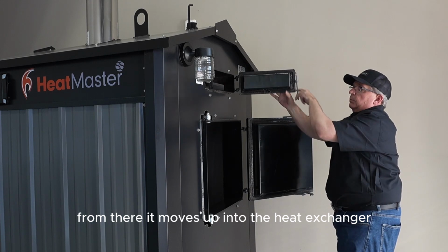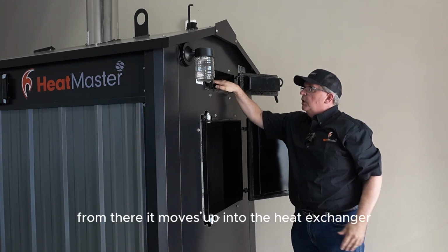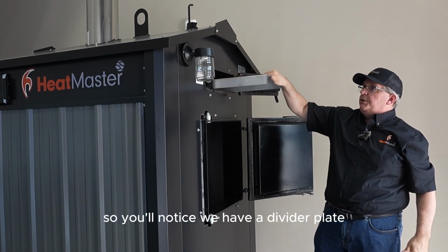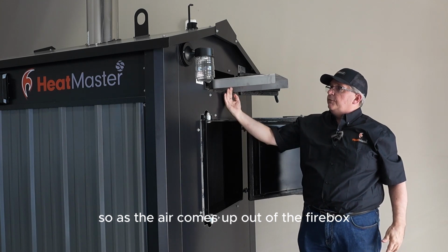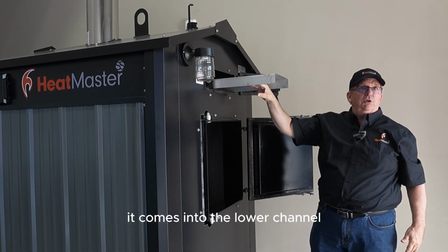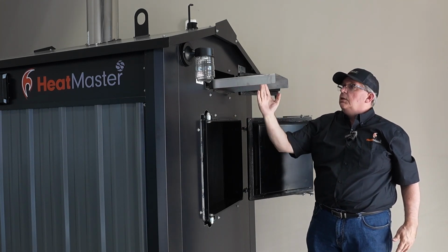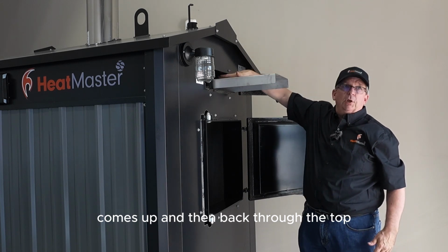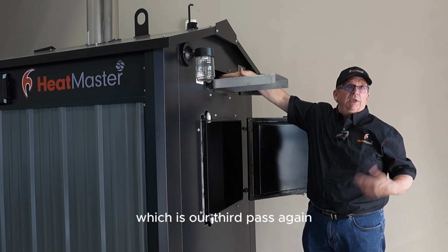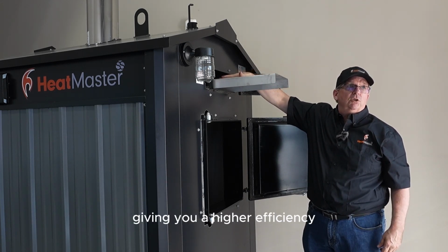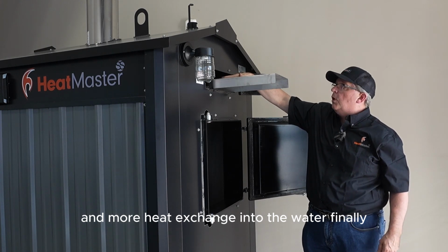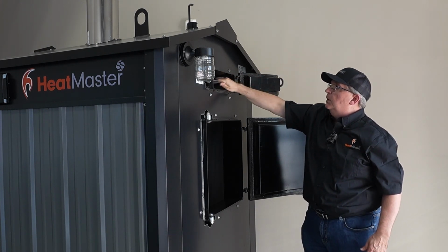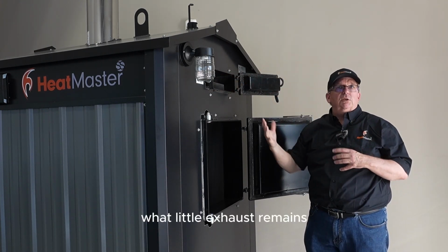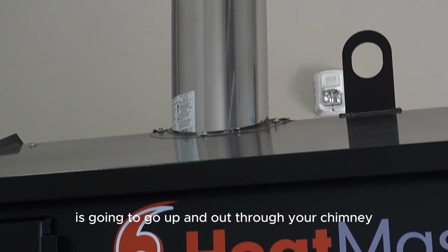From there, it moves up into the heat exchanger. So you'll notice that we have a divider plate. As the air comes up out of the firebox, it comes into the lower channel, which is our second pass, comes up and then back through the top, which is our third pass. Again, giving you a higher efficiency and more heat exchange into the water. Finally, what little exhaust remains is going to go up and out through your chimney.